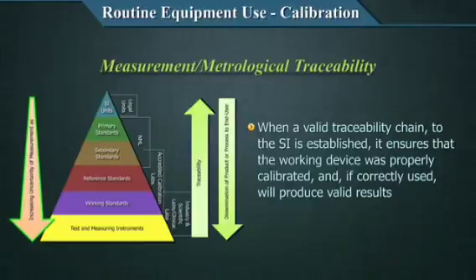Going back to the picture, you see the chain of comparisons starting from the SI primary standards, going to the secondary standards, through reference standards and working standards to the measuring instruments. If you look at the right side, you see this arrow going up, which is the traceability of the material or mechanism that you are using for your comparison. And the arrow that's coming down here is the dissemination of the standard. So the traceability goes upwards, dissemination comes downwards.